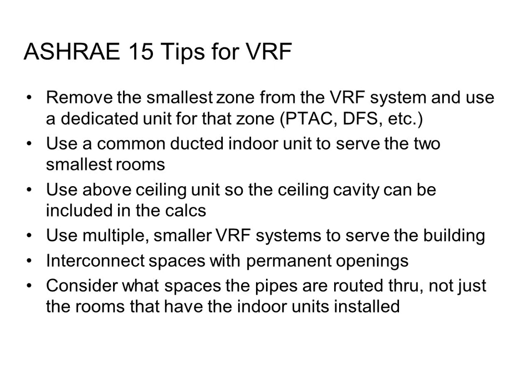In both of those cases, the software tools that we use to lay out the system will calculate the refrigerant volume required, and we give that volume to the installing technician so we can weigh that amount of refrigerant into the system. Now, the hard part is that if in the field they decide to run the piping a different way than we, meaning you and I, agreed on laying it out, then we need to know that from them so we can give them a different refrigerant calculation. But that data gets calculated by the refrigerant piping design software, which is where you get that number from.